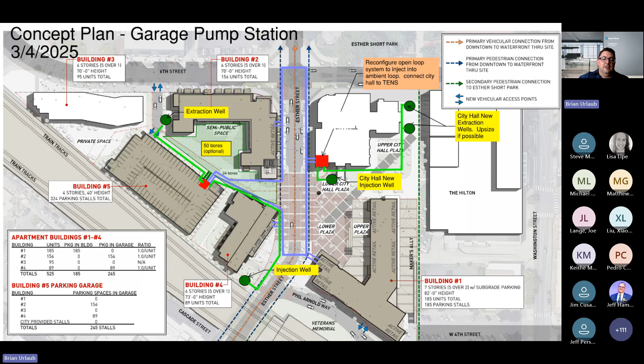What that does for us is it really drives down the ambient loop flow rate, because we have an open loop with a stable supply temperature. Now we can go from the 5-degree delta I talked about to a 10 or 12-degree delta, and everybody's still extremely efficient, yet we can reduce our pump horsepower and pump size dramatically.